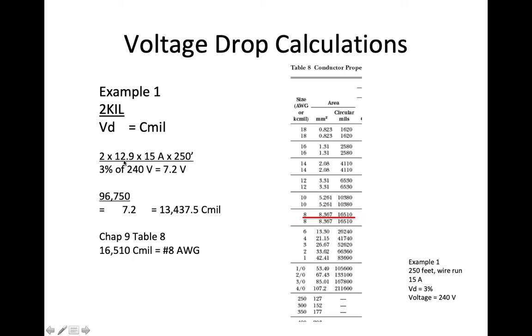If I have copper, my K constant is always 12.9. Now I'm entering in my current that I need. I need to get 15 amps over a far yonder distance of 250 feet away. I'm going to have 3% of 240 volts, which is 7.2 volts. So I multiply 2 times 12.9 times 15 times 250. That equals 96,750. The denominator is going to be 7.2. I divide 7.2 into 96,750, and it equals 13,437.5 Cmils.